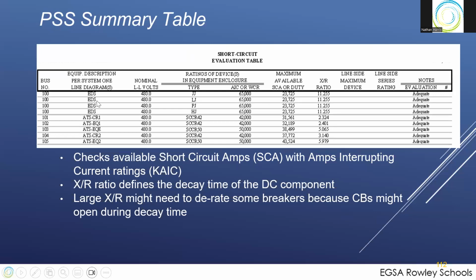And so we're looking at each device in the system and the ratings. In this case, it's AIC, amps interrupting current, or WCR, withstand current rating. Remember, we talked about the asymmetrical part of the curve. The X double prime D calculation was the peak value of current, and the X prime was where the breaker has to clear. And so that's the AIC rating.